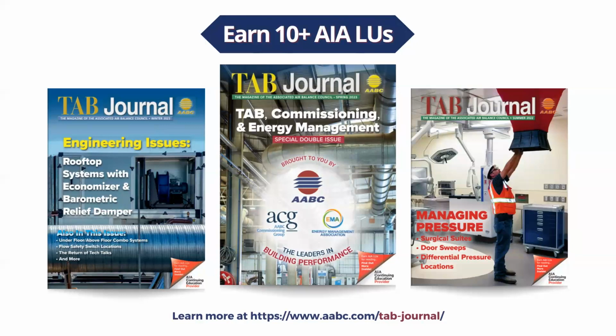From one of our members: do the dynamic valves operate independently, or are they, quote, managed by the BAS logic? So pressure independent valves, that's a good question. Pressure independent valves are dynamically balanced, but they are still a control valve. They will take that 2 to 10 or 0 to 10 signal from the BAS just like a standard control valve, but instead of equating that to 0 to 100% open, it would be 0 to 100% of the rated flow for that coil.